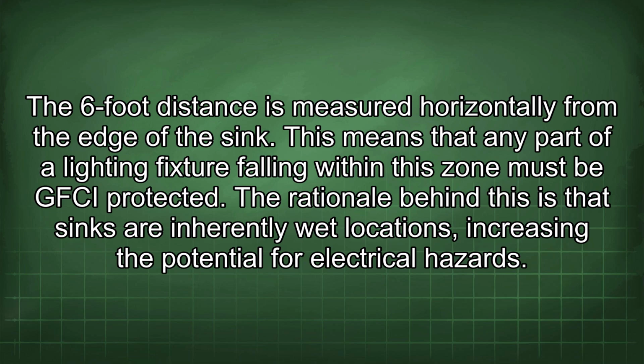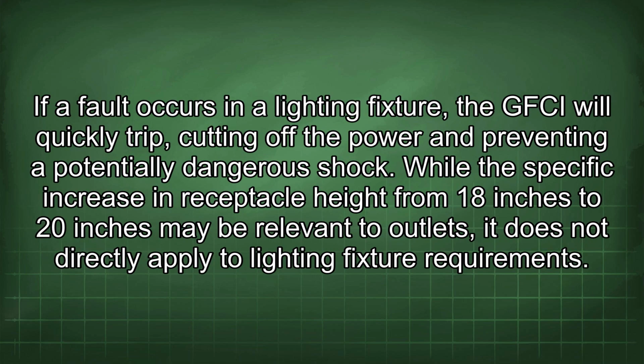The 6-foot distance is measured horizontally from the edge of the sink. This means that any part of a lighting fixture falling within this zone must be GFCI protected. The rationale behind this is that sinks are inherently wet locations, increasing the potential for electrical hazards.